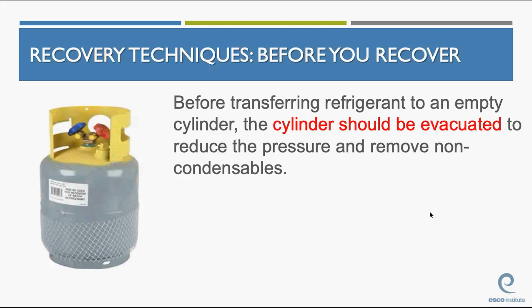Before transferring refrigerant to an empty cylinder, the cylinder should be evacuated to reduce pressure and remove non-condensables. Folks, before you use a new cylinder, throw it on a vacuum pump. Most often they do come in a vacuum, but if they're not, and if you have any doubt whatsoever that there's air in the system or in the tank, put it on a vacuum and let the vacuum run for a while to remove the non-condensables, remove the air, remove the moisture, and also reduce the pressure. The lower the pressure in the recovery cylinder, the faster the refrigerant recovery is going to be. Okay, so just get the air out of the system, get the non-condensables out of the systems.